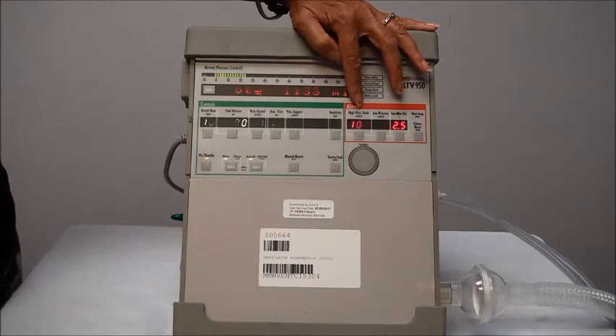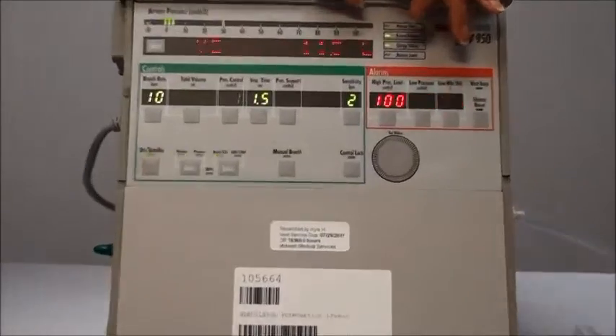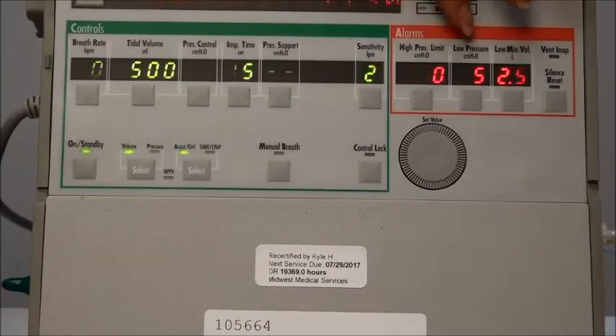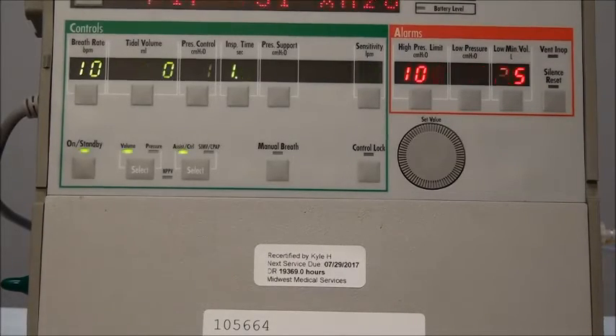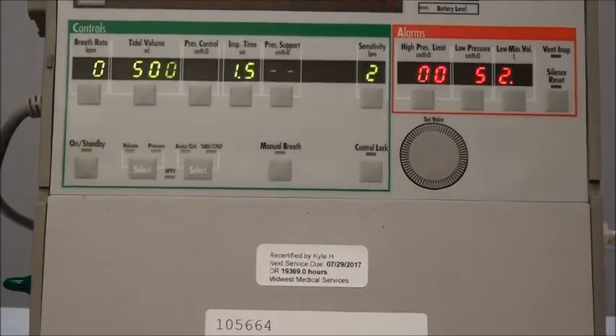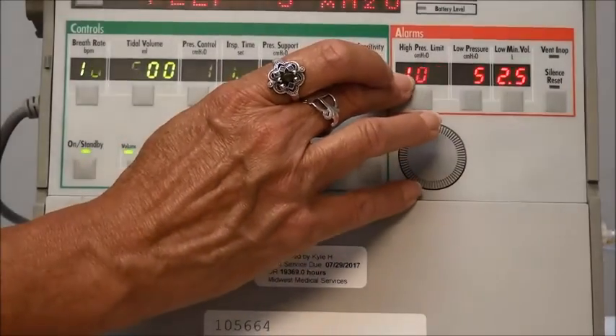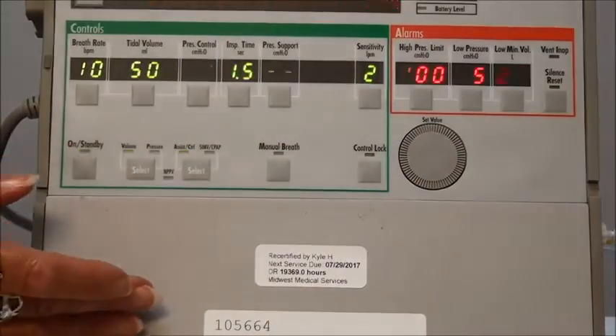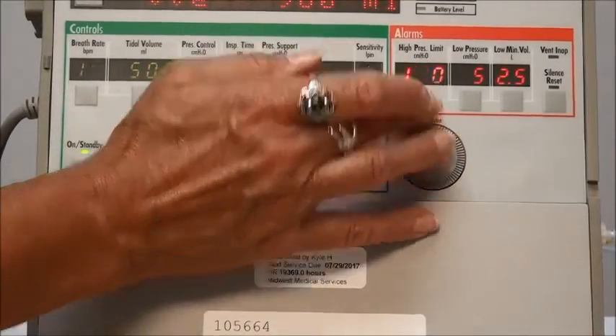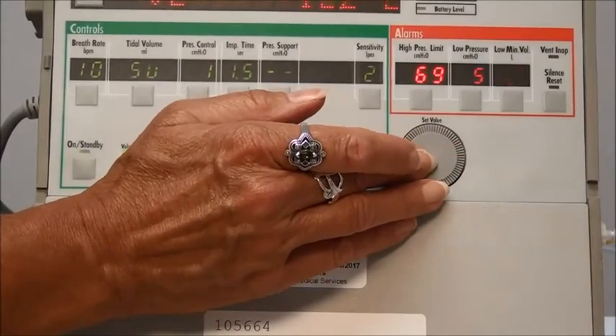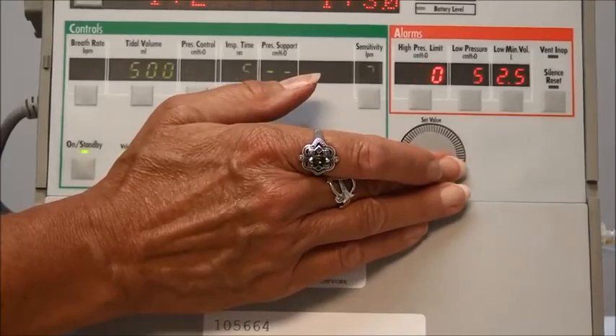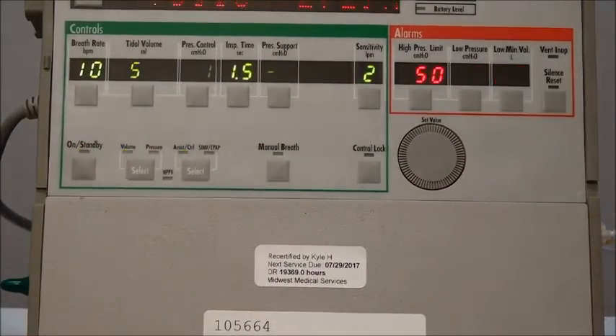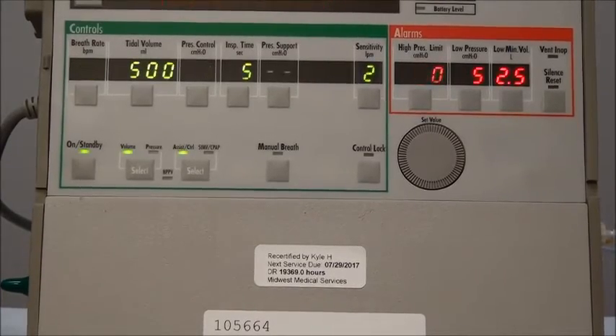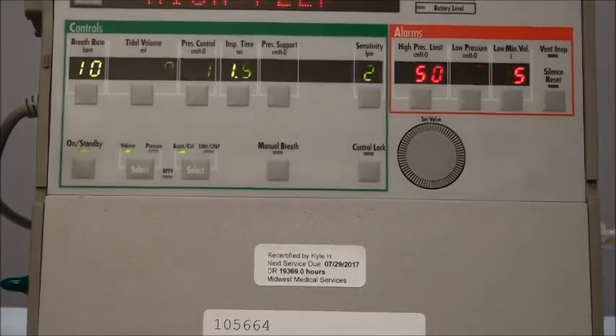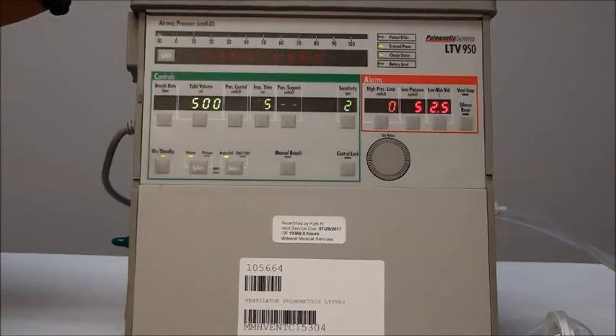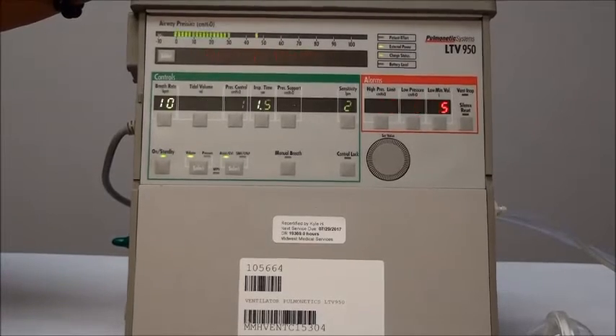Now over here, we have your alarm settings. We have, and we talked about this earlier, your high pressure, your low pressure, and your low minute volume. So a high pressure alarm, if you got a high pressure alarm, your pressure would have to go above what is set here. Now right now it's set at 100, which is something you're probably not really going to see. So I'm going to turn it down to something that would be a little more reasonable, depending on what your patient's pressures are. I'm going to make a high pressure alarm. So this is giving me a high PEEP alarm, which is one of your internal alarms that I was talking about earlier that doesn't show. And I'm also getting a high pressure alarm.